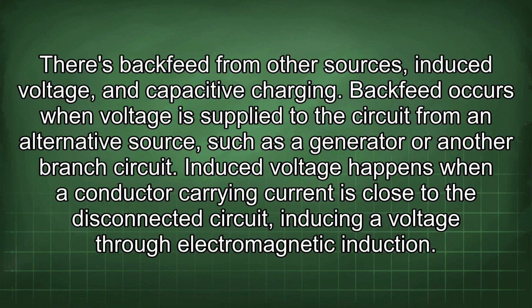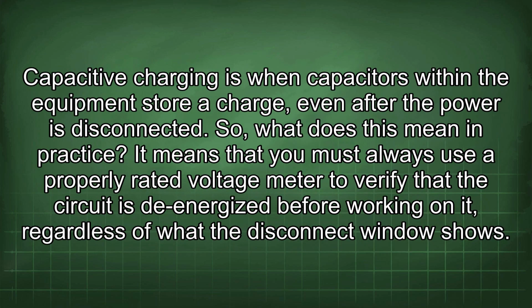There's backfeed from other sources, induced voltage, and capacitive charging. Backfeed occurs when voltage is supplied to the circuit from an alternative source such as a generator or another branch circuit. Induced voltage happens when a conductor carrying current is close to the disconnected circuit, inducing a voltage through electromagnetic induction. Capacitive charging is when capacitors within the equipment store a charge, even after the power is disconnected. So, what does this mean in practice? It means that you must always use a properly rated voltage meter to verify that the circuit is de-energized before working on it, regardless of what the disconnect window shows.